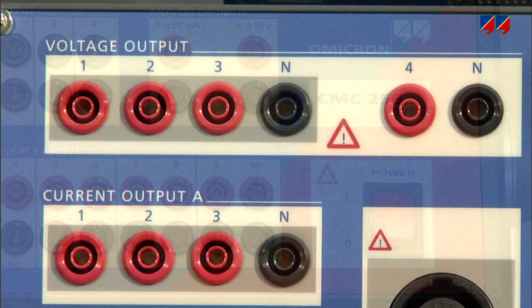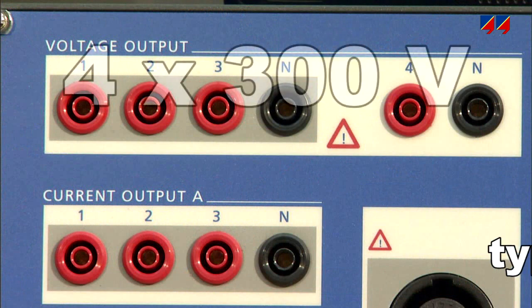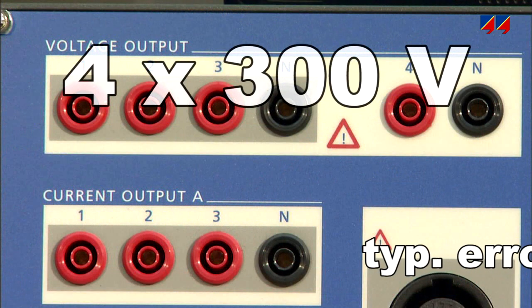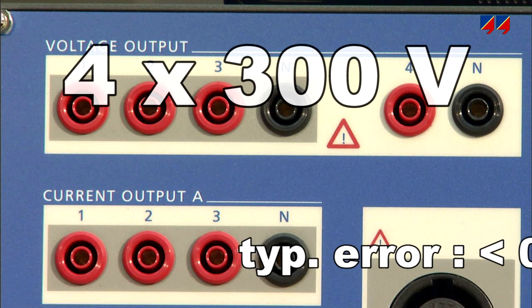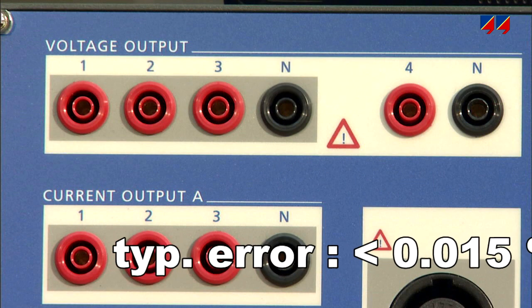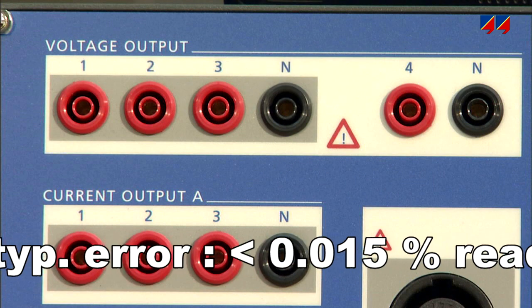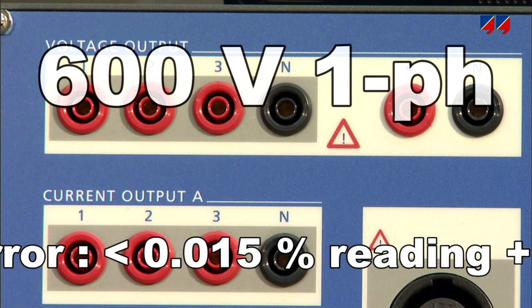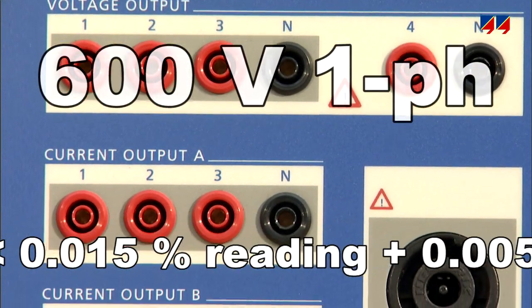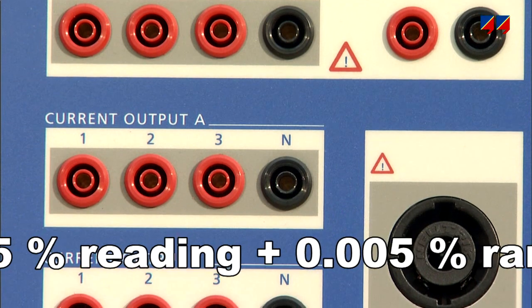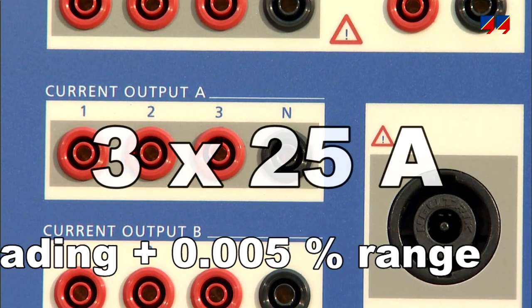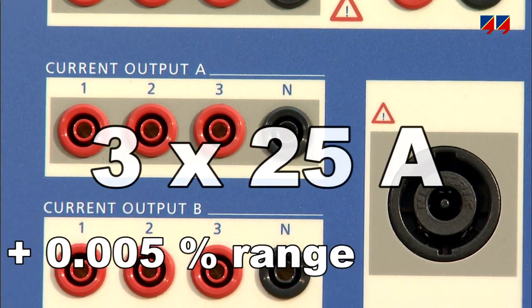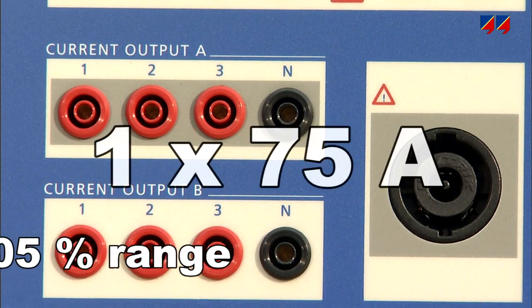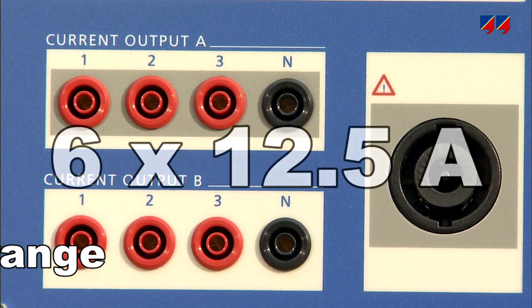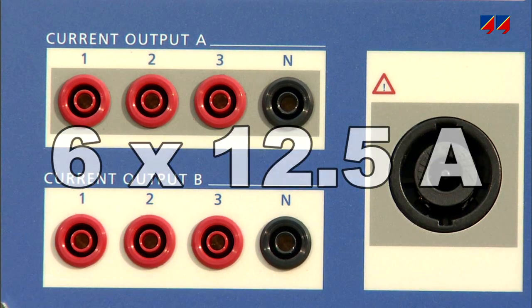The CMC 256 Plus includes four high-precision voltage outputs, which each generate up to 300 volts phase-to-ground, or 520 volts phase-to-phase, or up to 600 volts in single-phase mode. The high-precision current outputs can provide up to 3 times 25 amps, or 1 time 75 amps, or 6 times 12.5 amps.